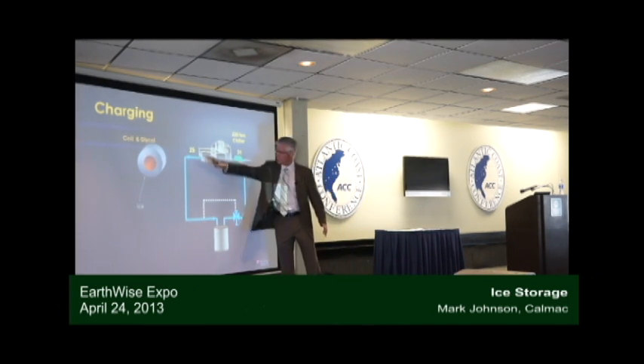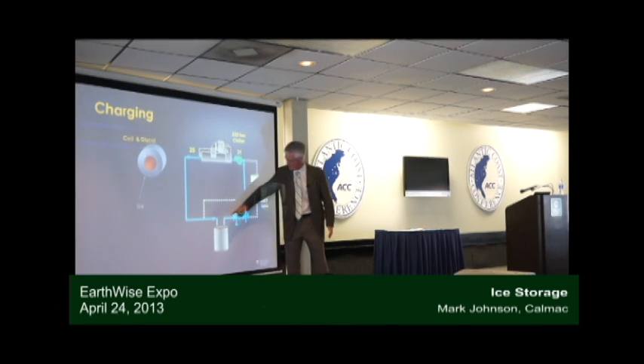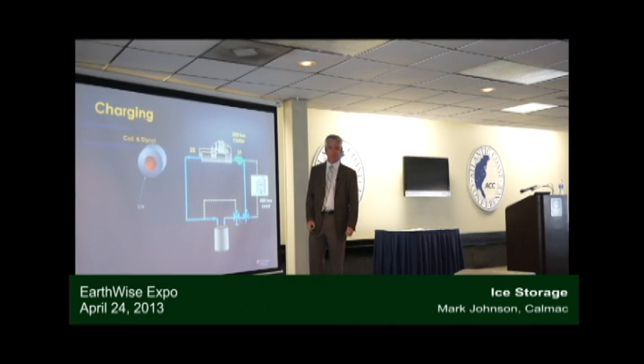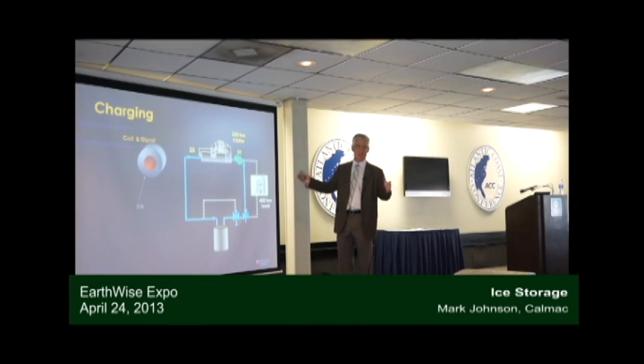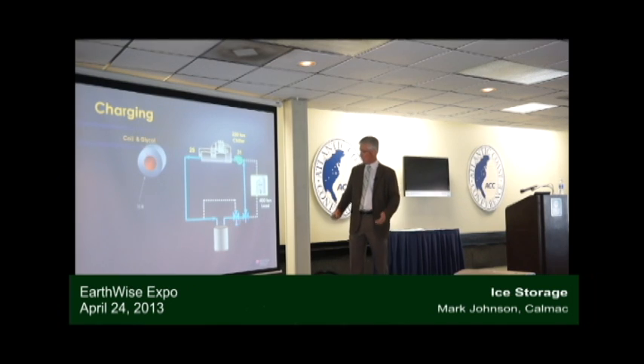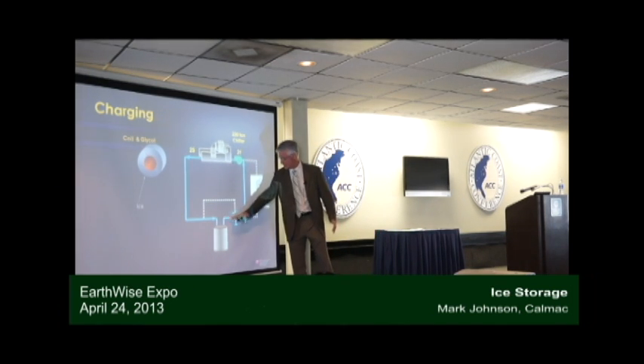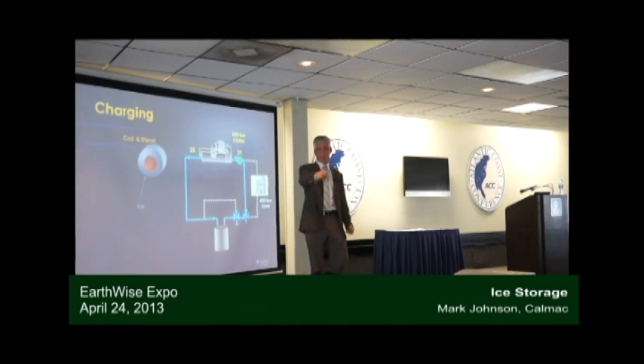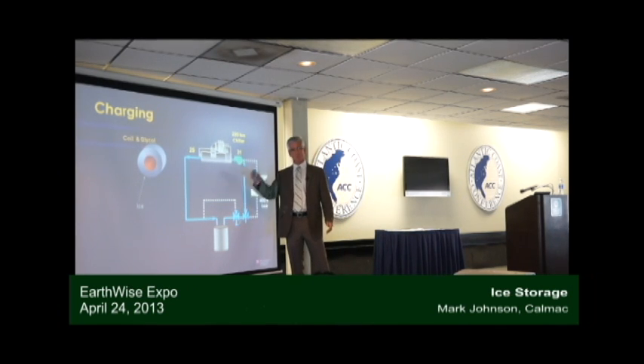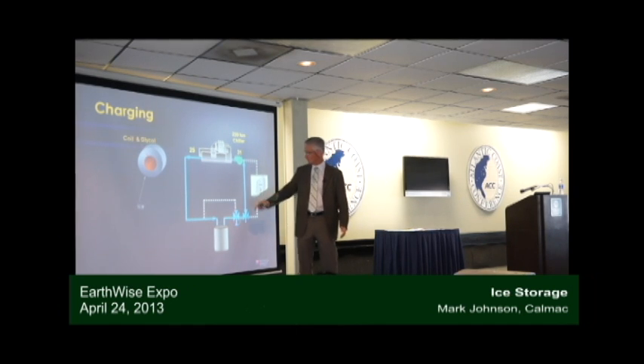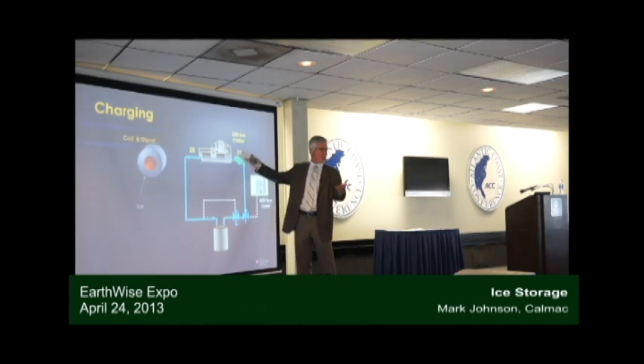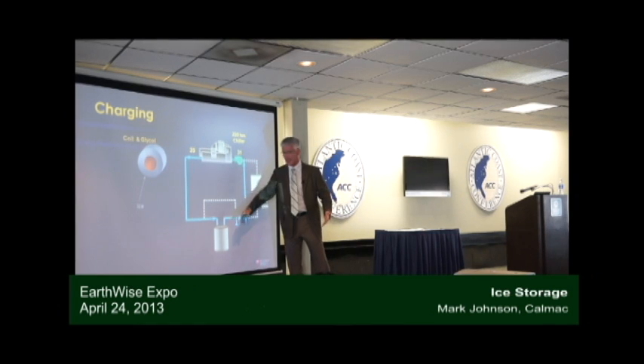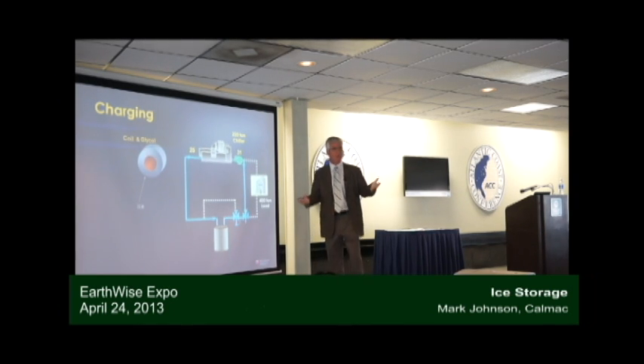And that 25 degree glycol and water solution is going to go through those tubes and it's going to build ice. And that's going to take between 6 and 9 hours typically, depending on how much ice you used the night before. When this temperature right here is about 26 degrees, what do you guys use? Right here, that shut-off temperature. 28 return. When that return temperature is in the 26, 28, it depends on the chiller and ice combination that we have, we're done making ice.